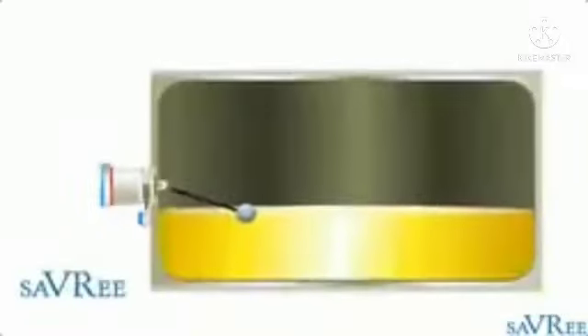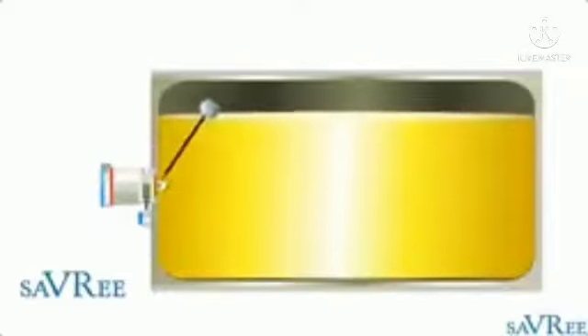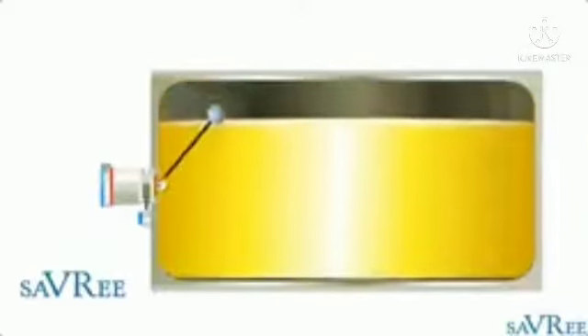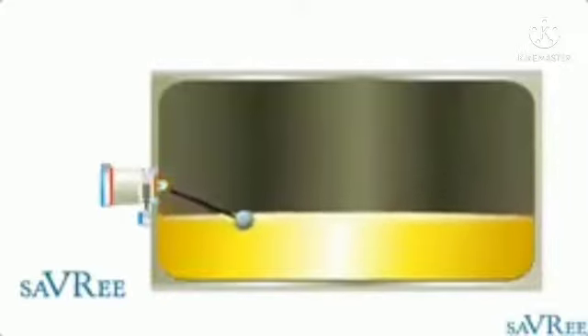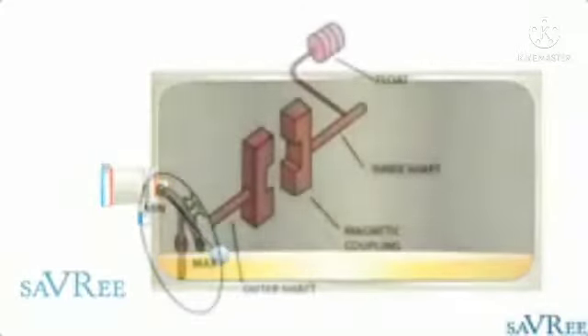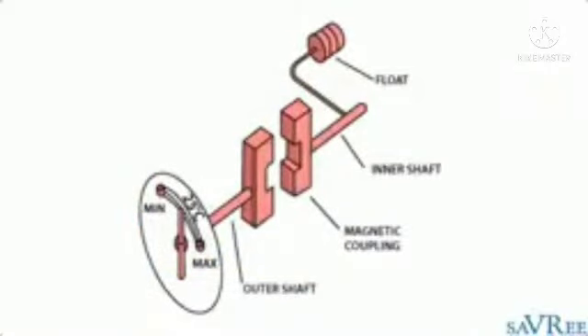If we look inside, I can show you the working lever. So there is the lever or the float, and you can see that as the level would increase, the float would be pushed upwards, and as the level decreases, the float would sink back down again. So that's how it works. Just remember though that this lever and float is not connected directly to the outside gauge. It's actually connected magnetically. It's coupled magnetically. That's why it's called a magnetic oil gauge.